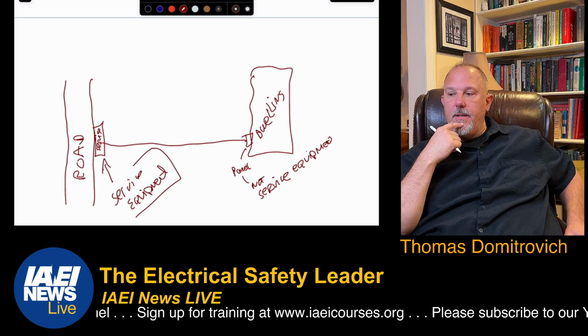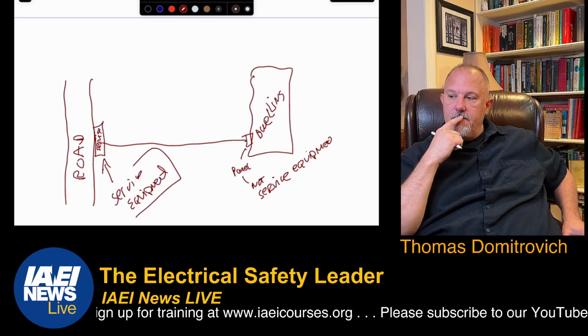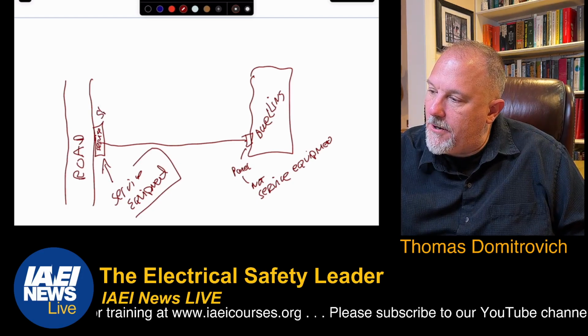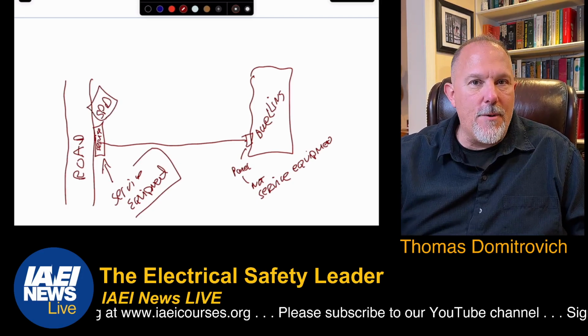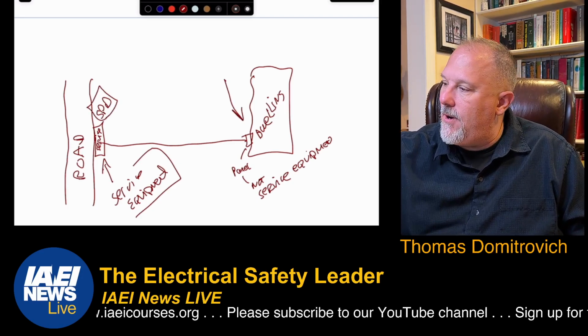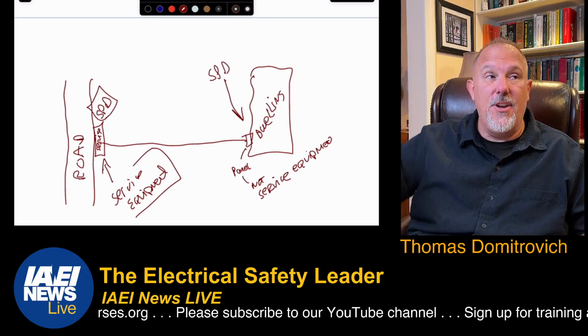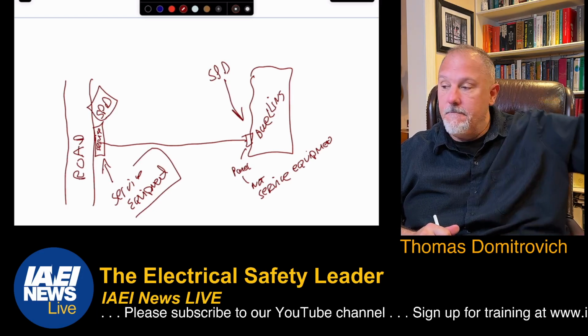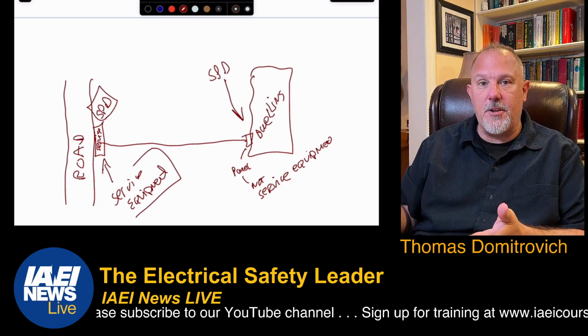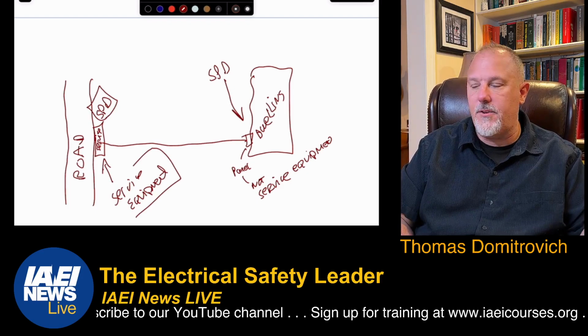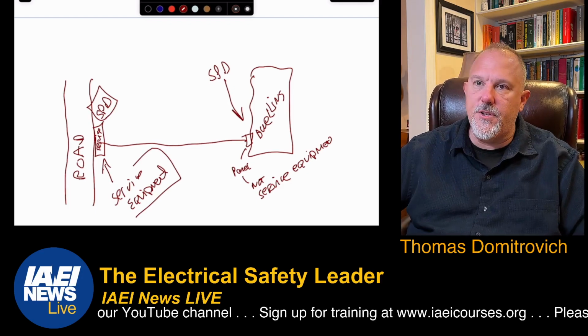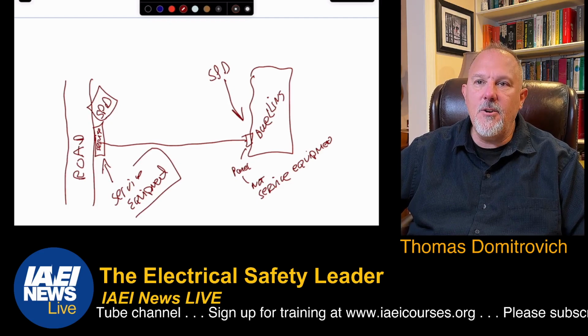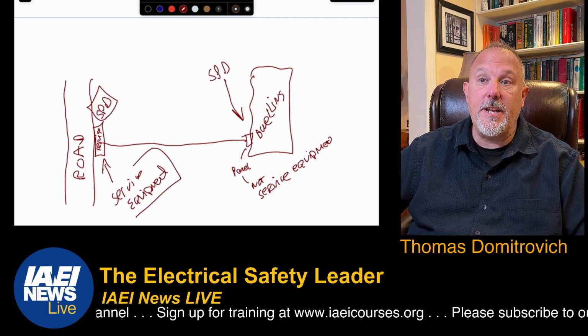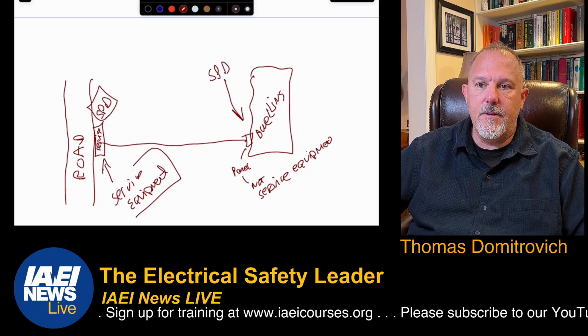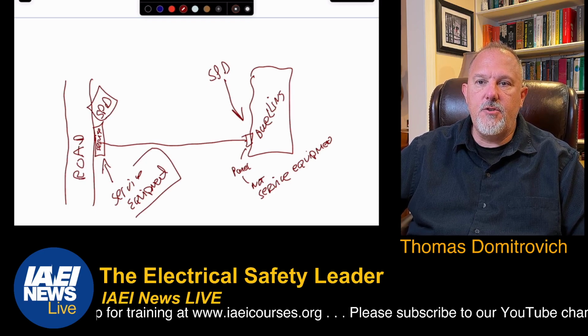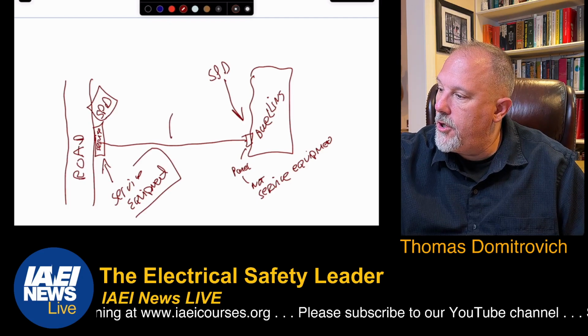What happens when I have a service out at the road? The SPD would be required here. But where do I really want it? I want my SPD down at the house, not out there at the road. I can have a lot of transients introduced to this dwelling unit, and that SPD out there at the road is not doing any good. So what did we do? We went into 225. We said, you know what? We need to make a change in 225. Where is it? 225.42.